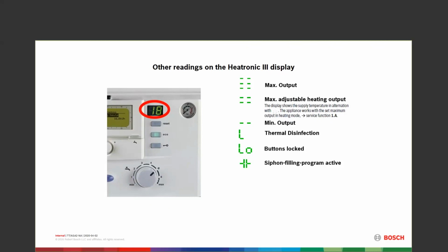Every time we turn the control power off and turn it back on, we go back into a siphon fill or trap fill program. It's a 15-minute program for trap fill that makes sure that our condensate trap is full of water all the time and doesn't have any problems being dry. That's why every time it's turned off, it goes back on. It also does it once every 28 days by default and can be adjusted to do more or a little bit less. It can be turned off in the control. I do not recommend turning it off. If you turn it off and you forget to turn it back on, it'll stay off. That trap can become empty and put CO out into the room, potentially harming one of your customers.